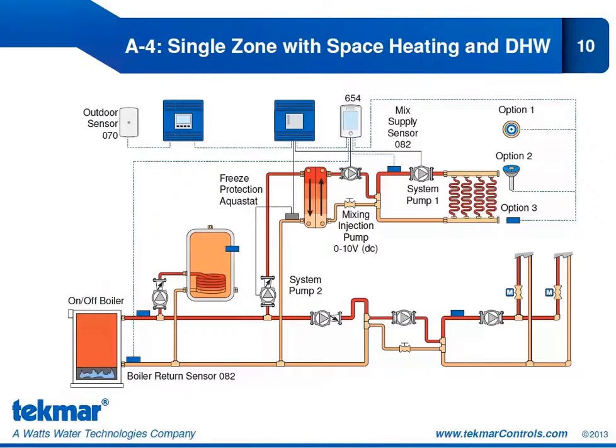Application 4 shows a single zone when we're combining our snowmelt system with a larger system that is operating some space heating and domestic hot water. So we have our 654 that's connected to a wiring center. The wiring center here will be connected to a house control. And the house control is going to be operating the on-off boiler, it's going to be operating the domestic hot water, this boiler system pump here, and it will also be taking care of the mixing for the space heating zones. So we'll take a look at the next slide in which we are shading everything that's being operated by the house control.